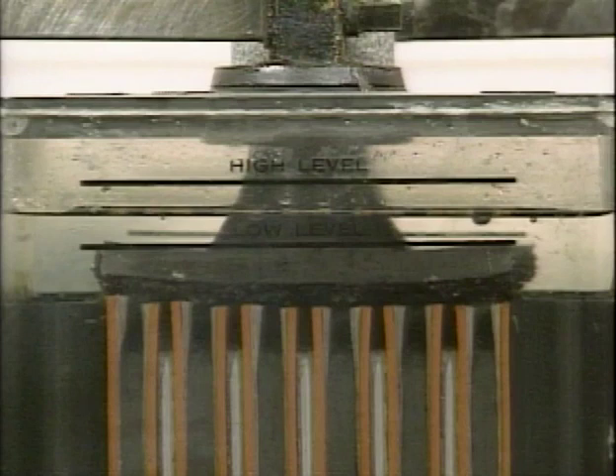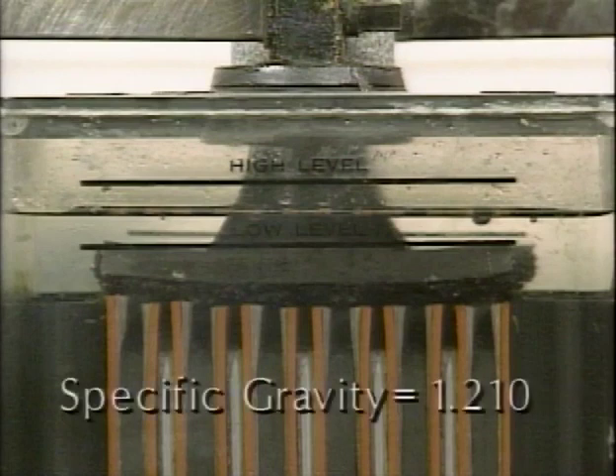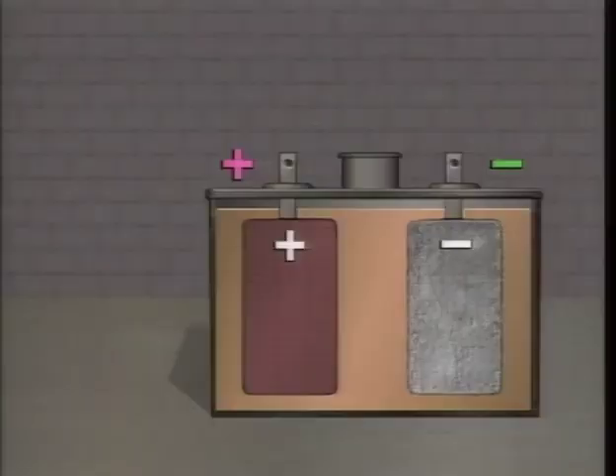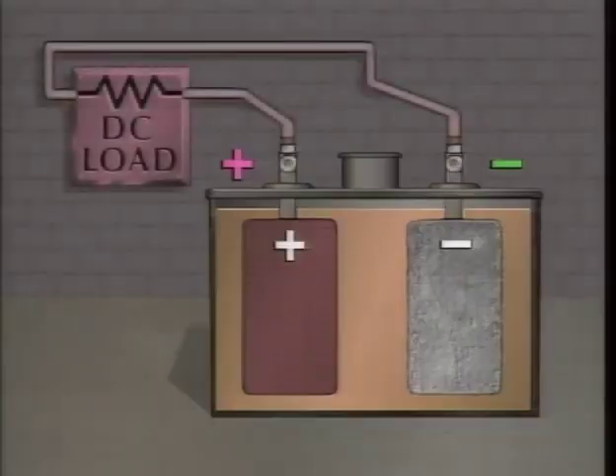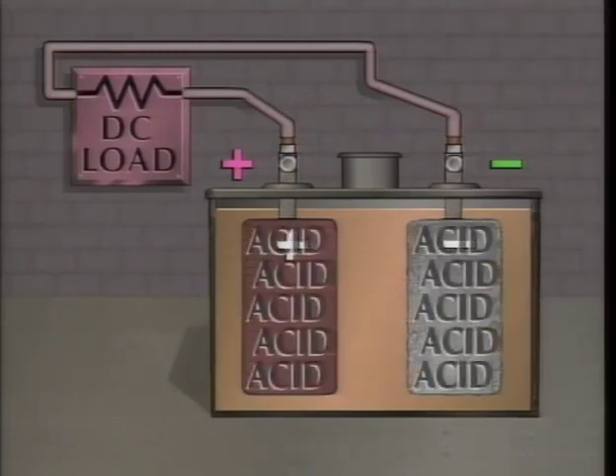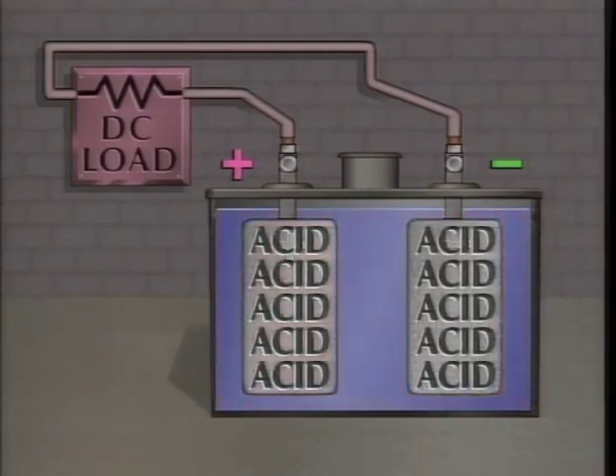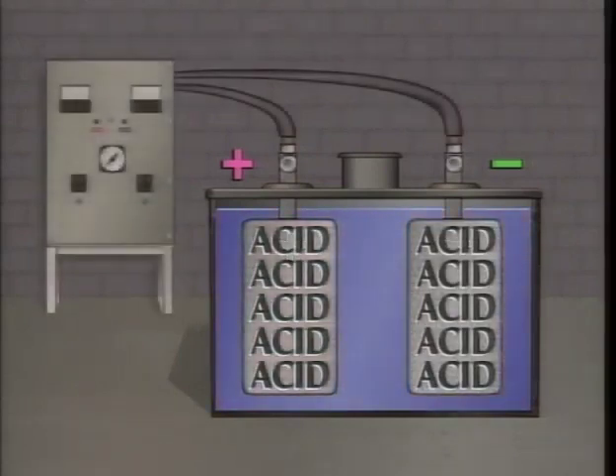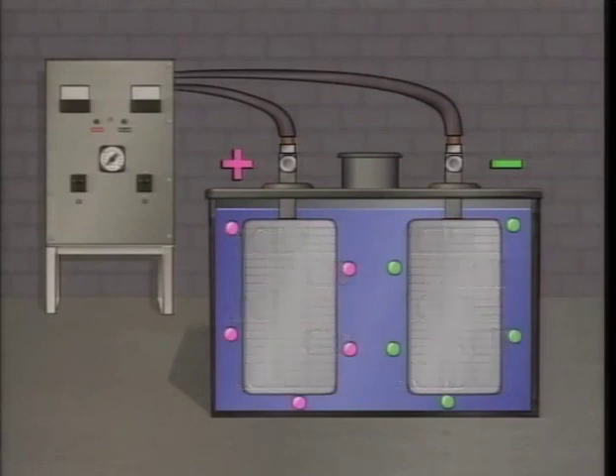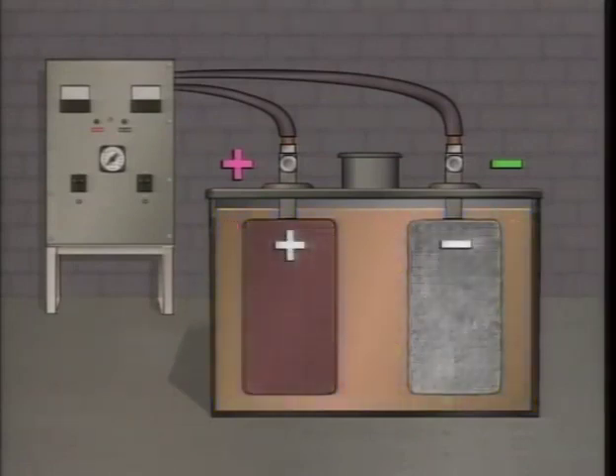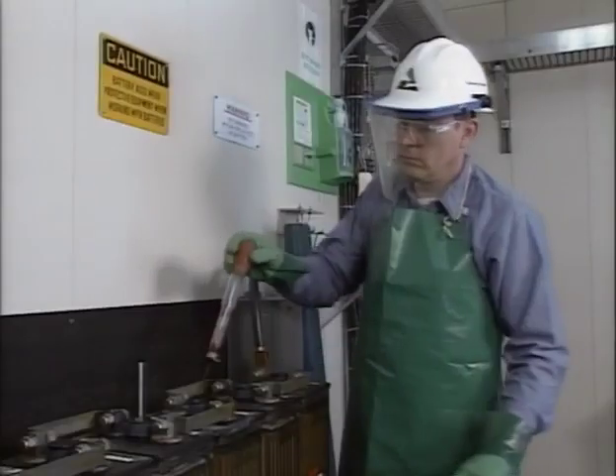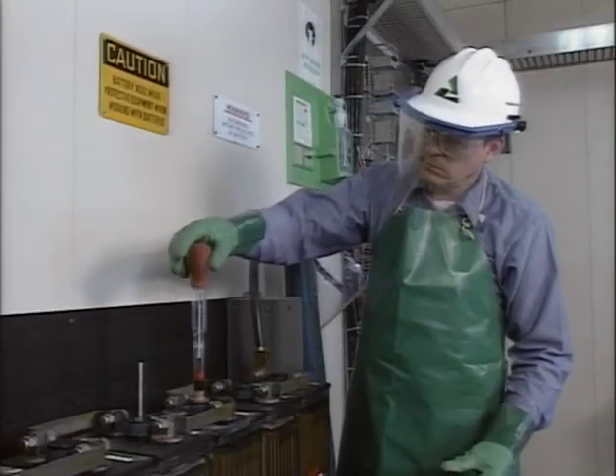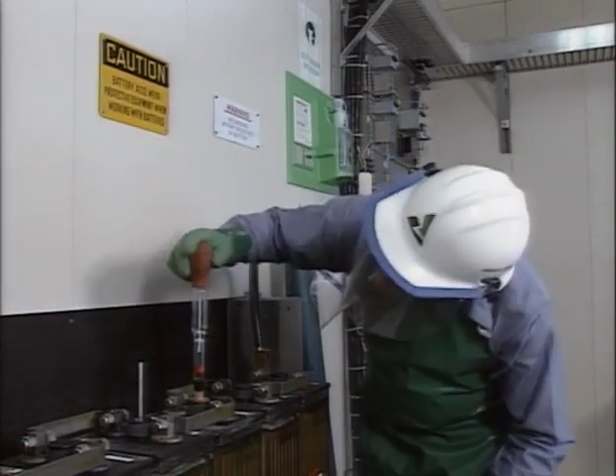As you may know, the electrolyte in a cell is composed of sulfuric acid and water, and the specific gravity of a charged lead-acid cell is typically around 1.210. You may also know that as a cell discharges, the specific gravity of the electrolyte decreases because sulfuric acid leaves the electrolyte and combines with the lead in the plates. As the cell is recharged, the specific gravity increases because the sulfuric acid is driven off the plates and back into the electrolyte. So, specific gravity testing is a useful tool for determining the state of charge of a cell.